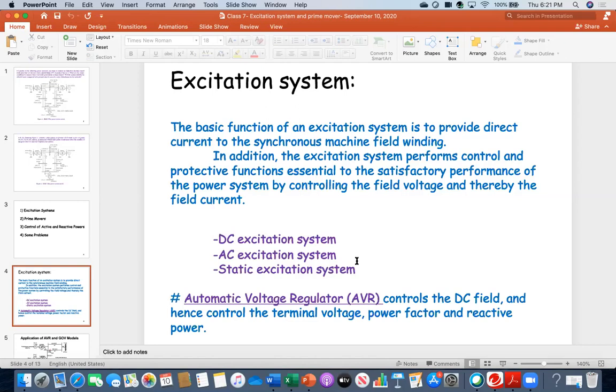That's why, in order to avoid this system, these days power engineers are preferring PMSG, permanent magnet synchronous generator. So what is the benefit? The benefit is that you don't need any of this system. You can install a permanently magnetized generator that stays magnetized for 30 or 40 years. Time to time you might need some overhauling and maintenance, but at least it will remain magnetized for 30 or 40 years, so you don't need any of this excitation system.